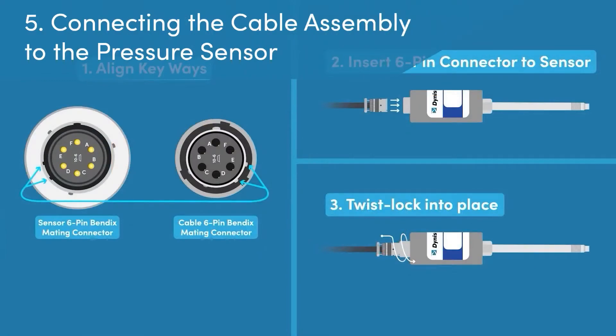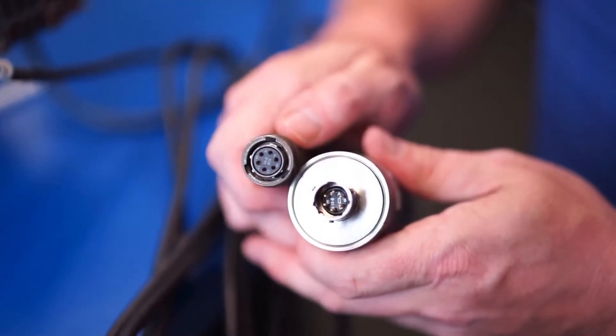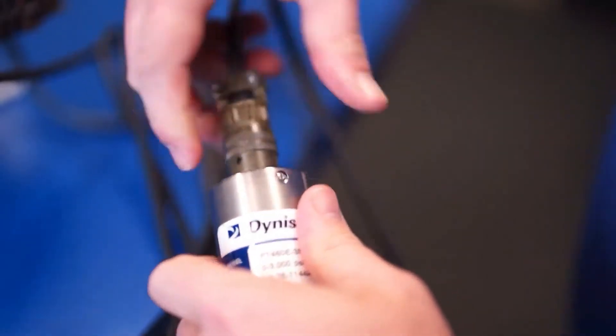Step 5: Connecting the cable assembly to the pressure sensor. Once the cable assembly has been secured to the screw terminals on the instrument, the technician will then connect the Bendix mating connector to the electronics of the pressure sensor. There is a key way that will allow for the connector to align with the corresponding pins correctly and then twist lock in place.